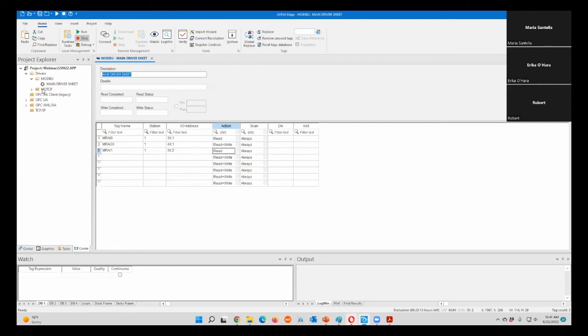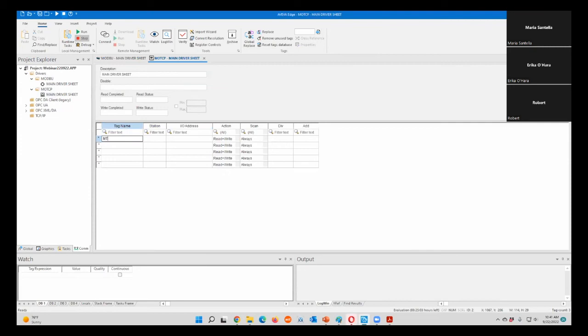Secondly, for the Modbus TCP connection, this is the second connection. We need to edit the main driver sheet and create our tags. We'll call this one MT for Modbus TCP, and this one's only analog input, so AI0. The station is the IP address, followed by the port number, followed by the Modbus ID. In this case, it'd be 21.127.198.230 colon 502, which is the Modbus port, and then colon 1, which is the slave ID. The address for the data is 3x colon 1.